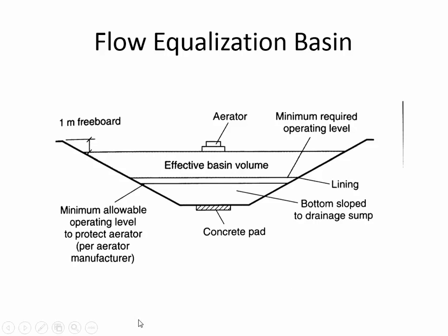Another important feature of a flow equalization basin is that there needs to be an aerator inside, because this is raw untreated wastewater with a lot of BOD in it. You're storing this waste before it enters the main treatment system, but it's still consuming oxygen. If you don't supply oxygen and it goes anaerobic, it can get really nasty — one of the gases from anaerobic waste is hydrogen sulfide, which is toxic, poisonous, and corrosive. So that's definitely to be avoided.